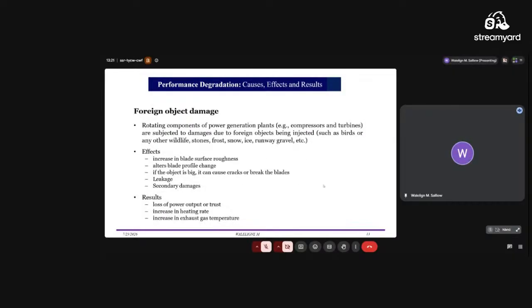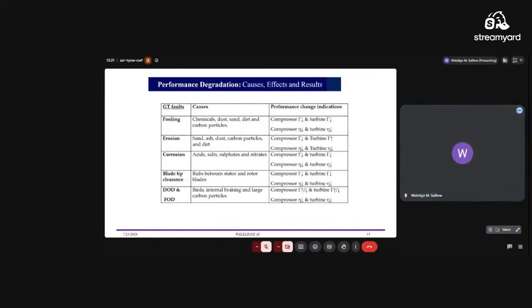And the other one is foreign object damage, which happens when foreign objects get into the gas turbine. For example, birds or other wildlife, stones, snow, ice, or runway debris entering the gas turbine. That increases the blade surface roughness, alters the blade profile, and if the object is big, it can crack or break the blades as well. So these are the most common gas turbine faults. The most dominant one is fouling, but erosion, corrosion, blade clearance, and foreign object damage may also happen.